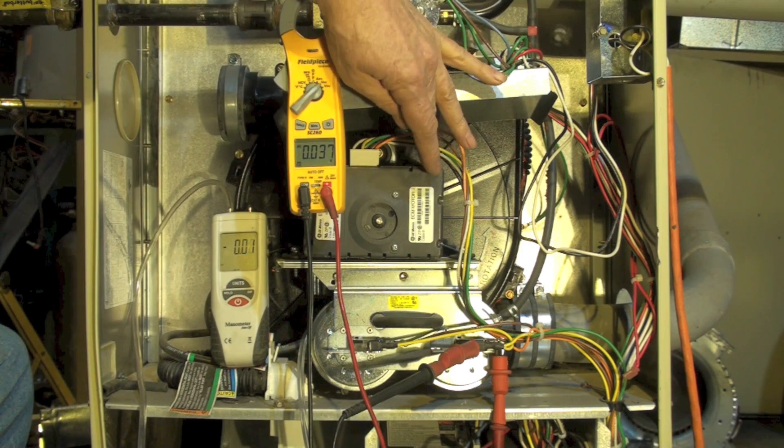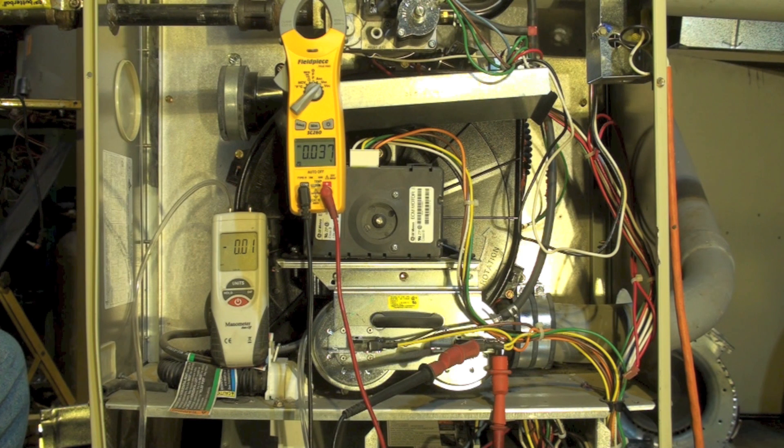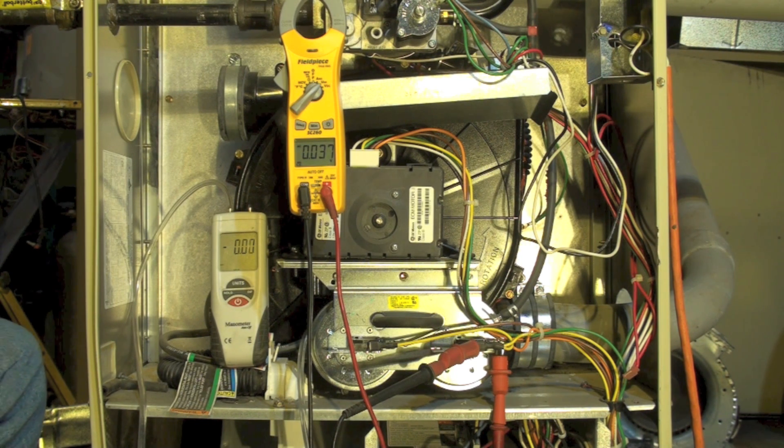What this variable speed inducer does is match its own speed with the venting. There's a certain amount of resistance in the venting and it's variable depending on how long and how many elbows are in it. It adjusts its speed to get a certain amount of vacuum.